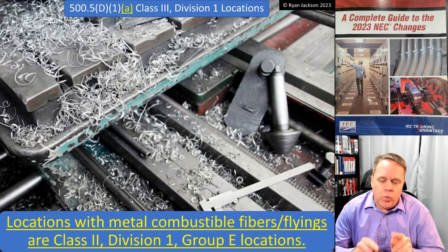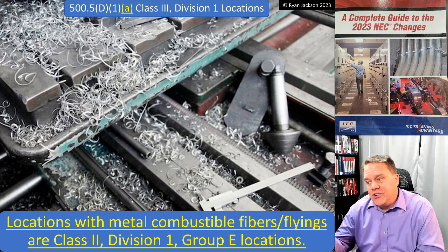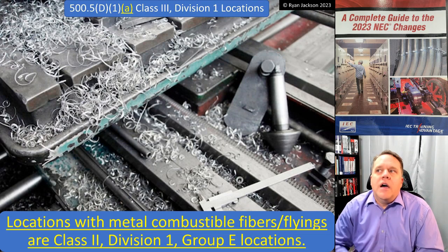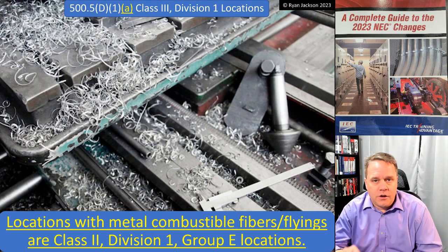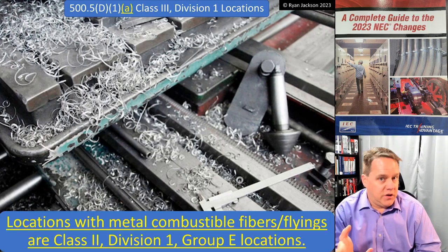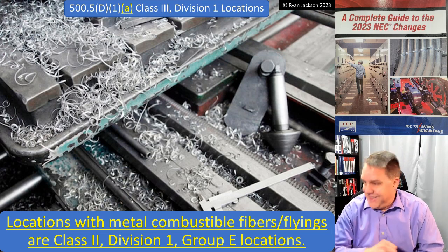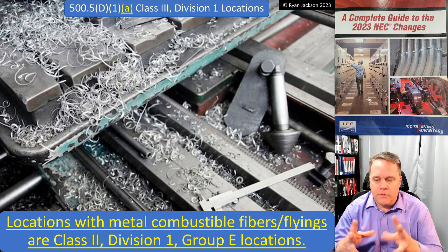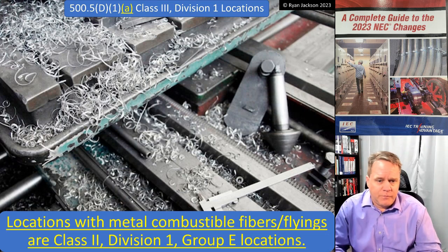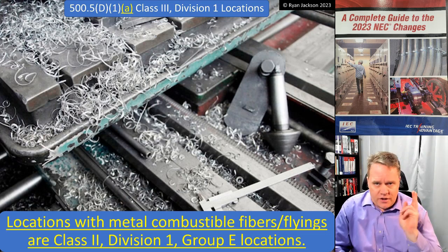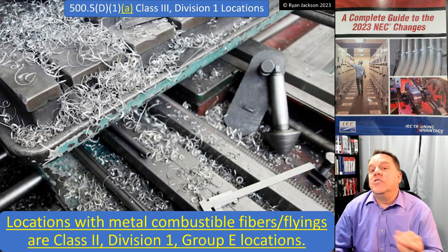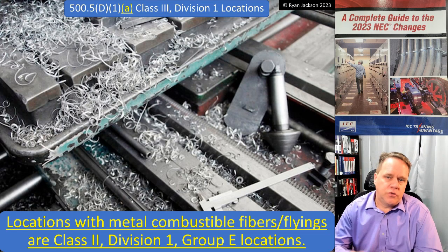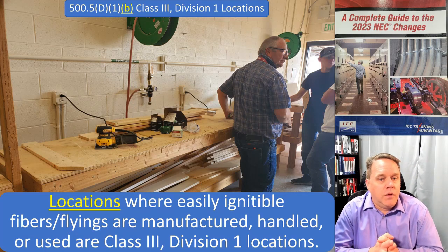A Class 3 location, between you and me, is less hazardous than a Class 1 or Class 2 — unless we're talking about metal. Aluminum dust, magnesium dust especially — when those go kaboom, they take down everything within sight. There was an explosion in China at a place that made aluminum alloys that completely leveled the facility. So when it comes to metals, you are automatically Class 2 Division 1 — there is no Division 2 if we're talking about metal.